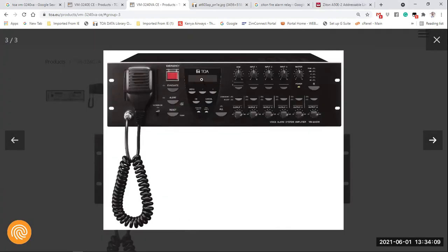Then whoever sees here, you can ask him, okay, you are on site, what is it saying? It is saying RM fault, then you know, before you even leave the office, maybe let me carry with me a spare RM just in case I've got any faulty RM. But your mindset, you will know, I need to carry a spare RM. I need to carry a few RJ45 plugs because somebody might have pulled the cable. I might need to recrimp it.